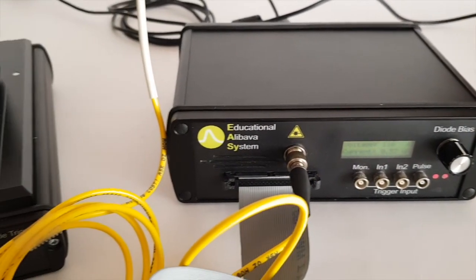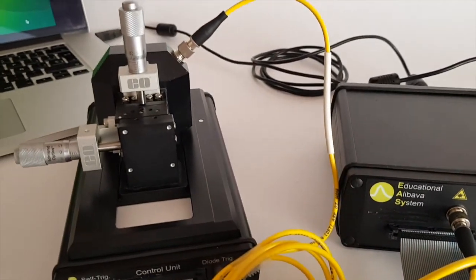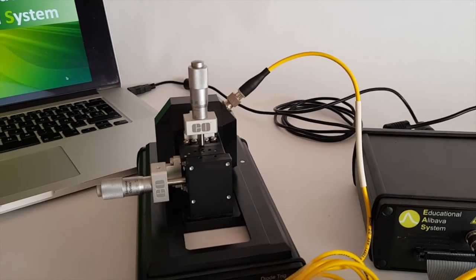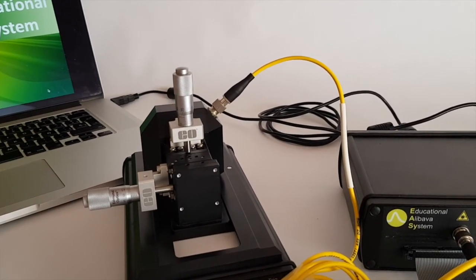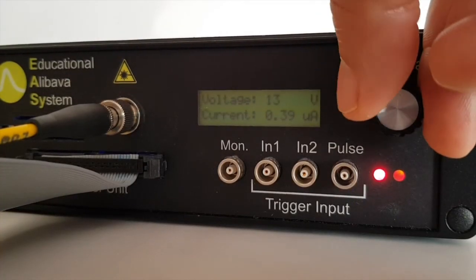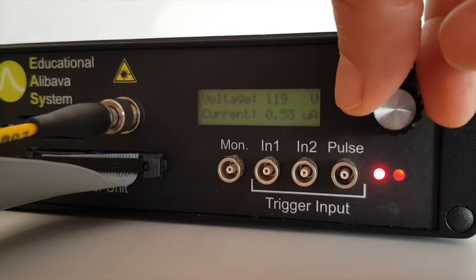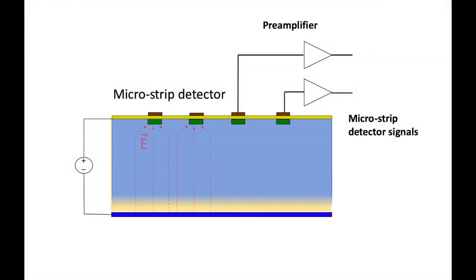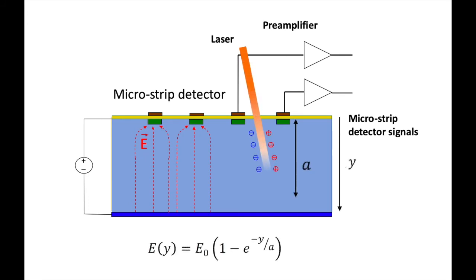Using the laser beam, the growth of the depletion zone with the bias voltage and the laser penetration depth can be studied by recording the charge collected for various bias voltages. The measured charge will be a convolution of the extension of the depletion zone and the energy deposition within the silicon. Since the laser energy deposition is exponential, the laser beam could stop in the detector bulk. The laser penetration depends on its wavelength.